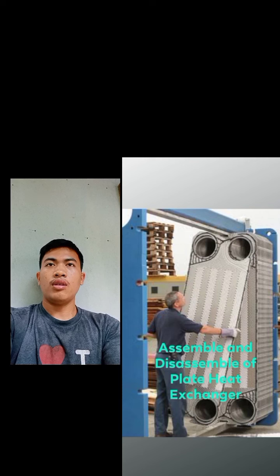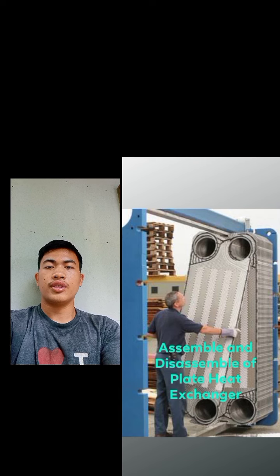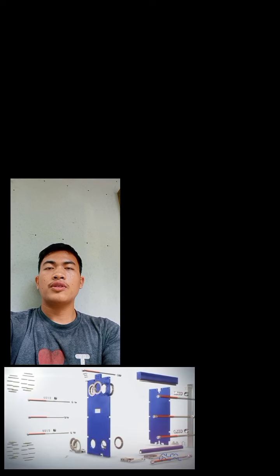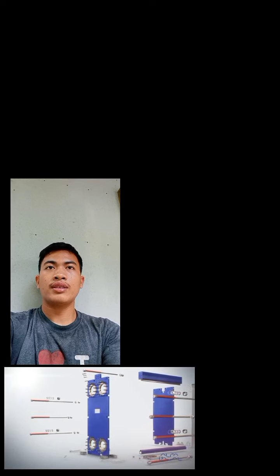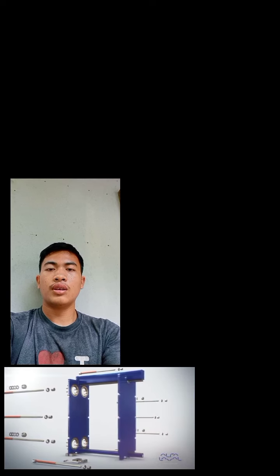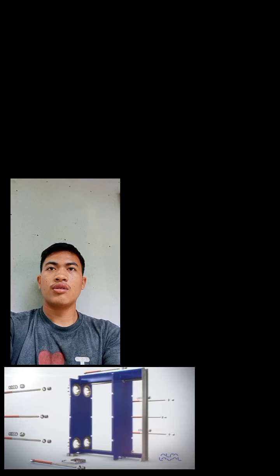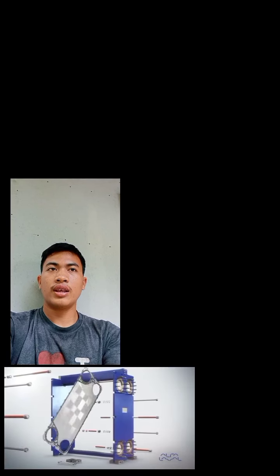And now I am going to make a vlog about an assembly of the plate type and tube type heat exchanger. An assembly of a plate heat exchanger. Number one, the pipe system is new or rehabilitated. Facilities need to be rinsed before mounting the plate. The heat exchanger soiling can cause blockage of the plate heat exchanger.